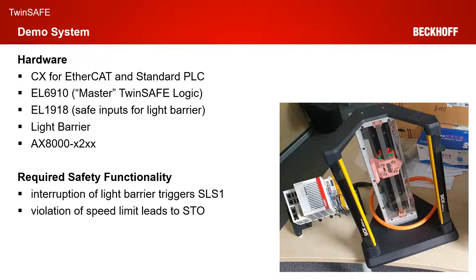From the safety functionality point of view, we want to realize a very simple safety loop. We have a light barrier, and the interruption of the light barrier should trigger safe limited speed on the AX8000. The AX8000 will limit the speed safely, and a violation of the speed limit should lead to STO on the AX8000.